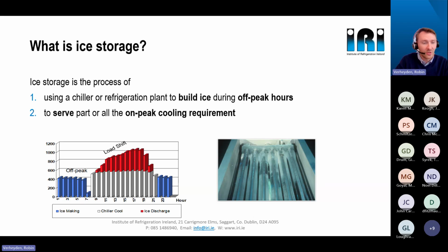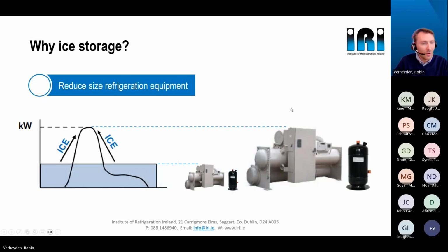That brings us to different reasons to use ice thermal storage. This method ensures your refrigeration equipment no longer needs to be designed for short peaks in the load profile, as shown in the graph, but can instead be sized for the smaller amount shown here. This results not only in a smaller chiller or refrigeration equipment size, but also reduces the amount of refrigerant used in your plant.